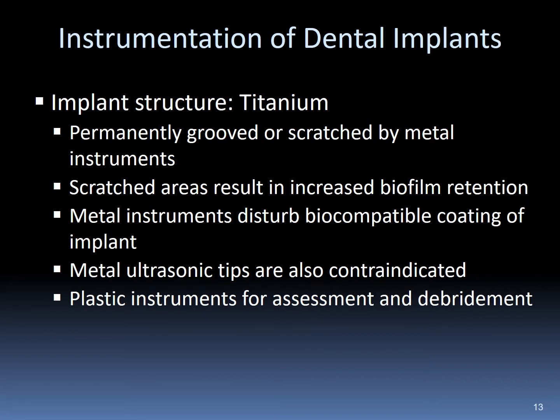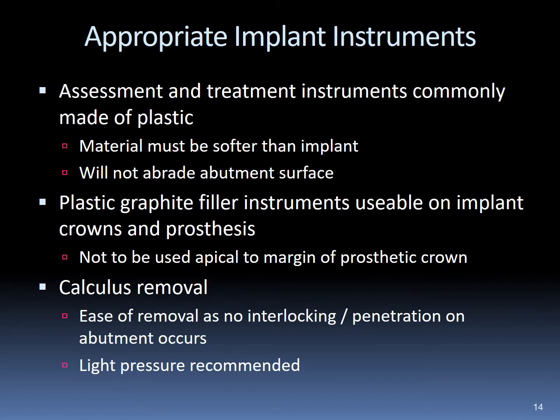The structure of dental implants is made of titanium. This metal is soft and can be permanently scratched with metal instruments. Scratches are believed to cause biofilm retention and disturb the biocompatibility of the implant's coating. Metal ultrasonic tips are contraindicated. Only plastic instruments are recommended for assessment and debridement, along with specially designed Cavitron tips. Assessment and treatment instruments for implants are commonly made of plastics; materials must be softer than titanium or the surfaces will abrade. Plastic graphite filler instruments are used on implant crowns and prostheses but cannot be used apically to the margins of the prosthetic crown.